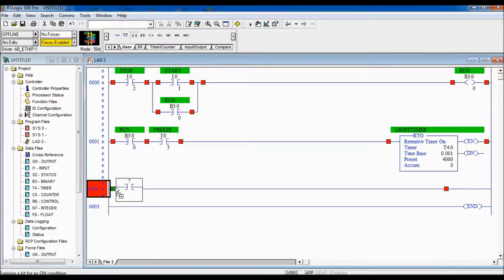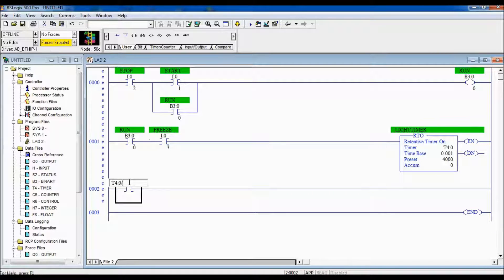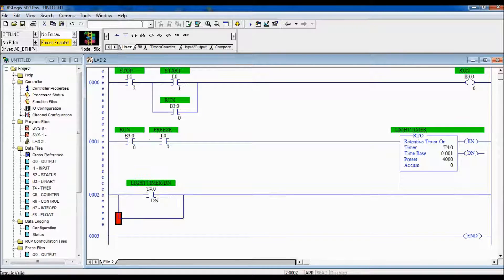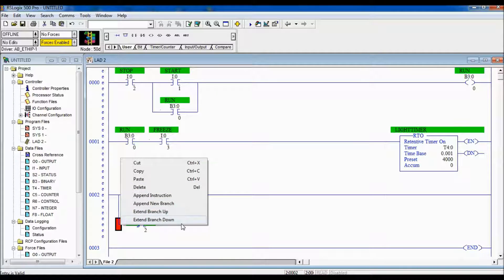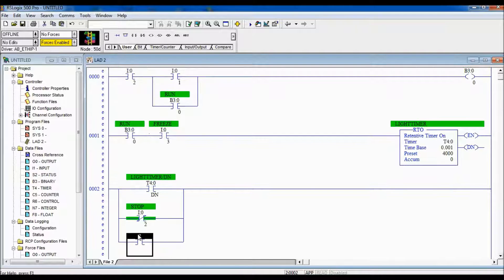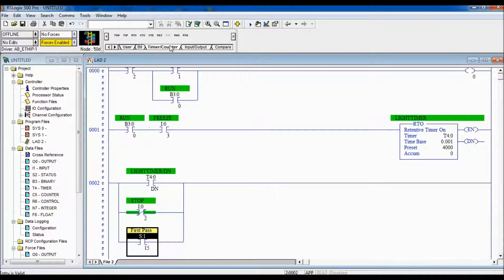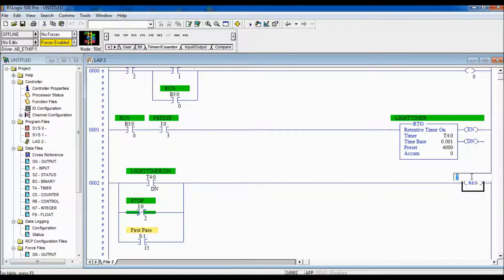So we have several instances: when the timer's done — T4 colon zero slash done — we're going to set it back to zero. We also want to do that when we press the stop push button, and remember the stop is wired normally closed, so we have to use examine if open for when it's actually pressed. We also want to do this when we first download or power up, using our first pass bit: S colon one slash fifteen. At that time, or any of these three conditions, we want to reset T4 colon zero. Remember it's retentive, meaning it keeps its value when the logic in front of it goes false.